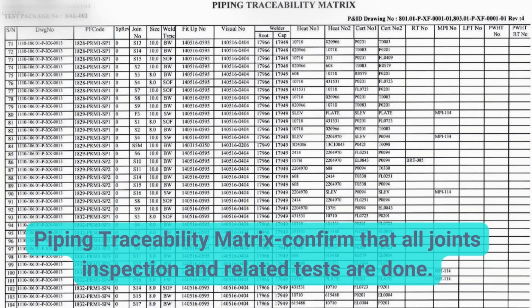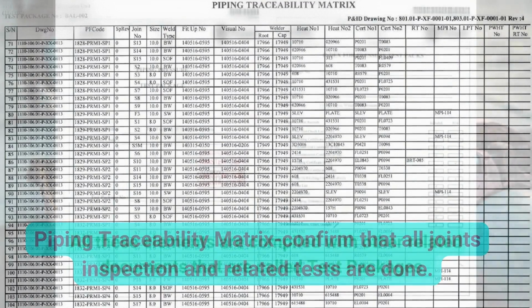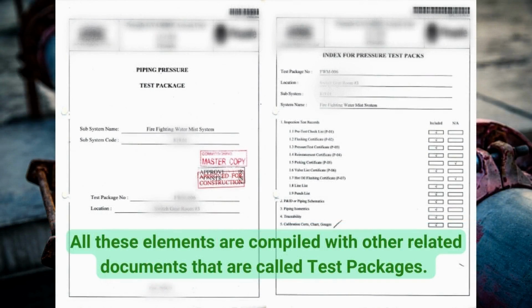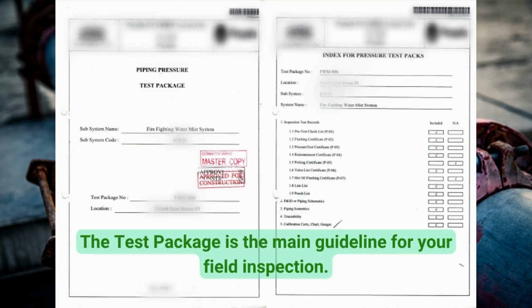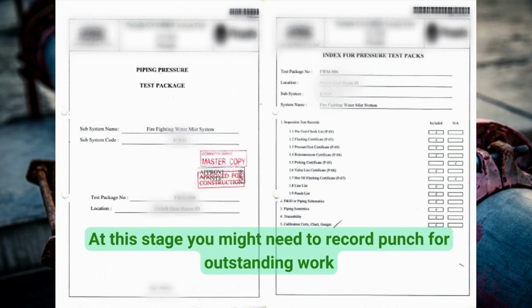Piping traceability matrix confirms all pipe joints, inspection and related tests are done and recorded. All these elements are compiled with other related documents that are called test packages. The test package is the main guideline for your field inspection. At this stage, you might need to record punch for outstanding work.